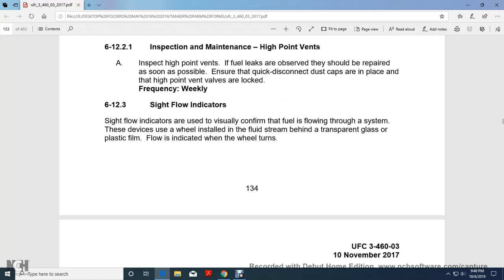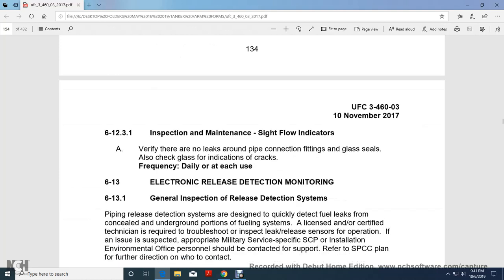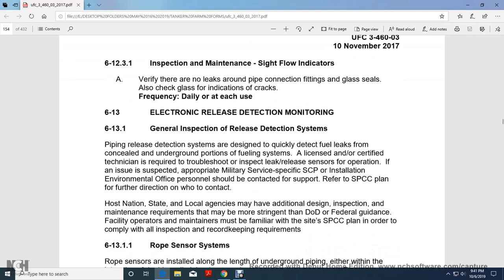Sight flow indicators are used to visually confirm flow through the system. The device has a wheel installed in the fluid stream behind transparent glass or plastic film. Flow is indicated when the wheel turns. 6.12.3.1 Inspection maintenance, sight flow indicators: verify there are no leaks around the pipe connection fittings or glass seal, and check the glass for indication of cracks. Frequency: daily or each use.